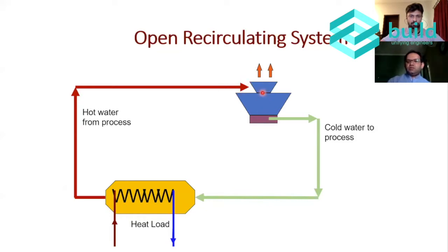During this cooling process, a lot of water evaporates, and the salts present in the water concentrate into the mainstream. So this cooled water becomes more concentrated, and when we circulate it into the heat exchanger, there's a greater potential for the tubes or plates to get fouled with suspended matter, since the cooling tower is open to atmosphere.